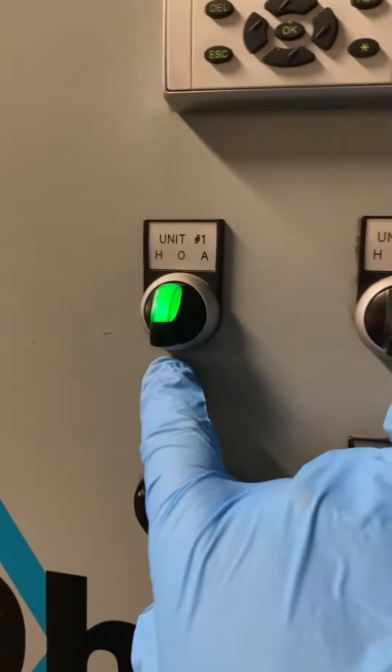Once you've done this, you'll see the HOA bypass, right? So this will still bypass and keep it running like that, but you can still run it in hand — that still works.